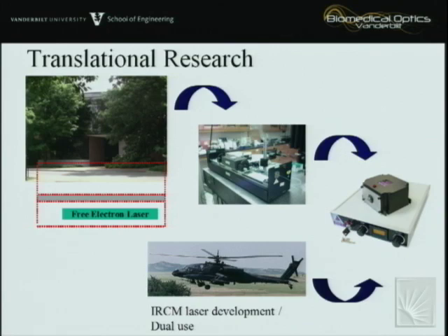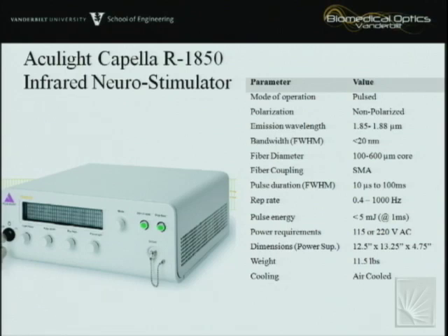As you see, it's got the laser driver and the laser head, so it's a two-piece. Pretty quickly, it became known as the bikini laser. From that initial prototype, we went to, I say we, this was largely done by Aculight, which last year got acquired by Lockheed Martin, and they have now developed this device, which really does look a lot like the optical version of a Grass stimulator. I won't go through the parameters here, but it's a little bit tunable depending on how hot you make the diode, and that's beneficial because it allows a little bit of optical tuning. Basically, this thing is twice the size of my laptop. You plug in the fiber, and you get buttons similar to what you'd find on a typical Grass stimulator: pulse rep rate, pulse duration, intensity, and so on. So this thing has been built. It is actually marketed and being sold now for research purposes.